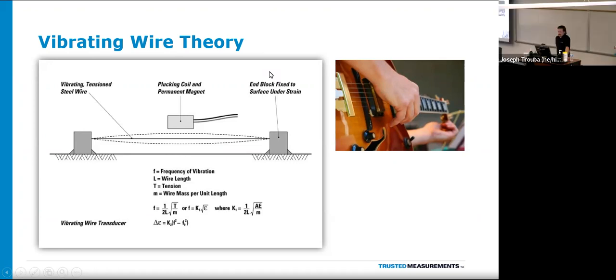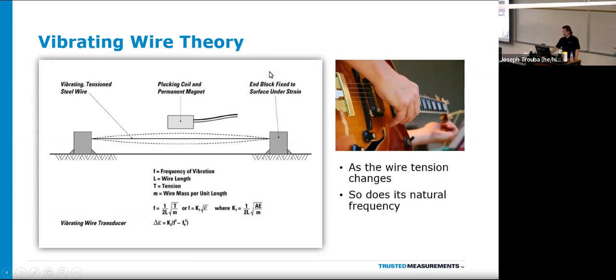And depending on the instrument, as pressure is applied to that instrument, or strain or any of the various parameters, it's going to change the frequency of that wire. As that wire elongates or shortens, it's plucked, and sends the frequency back to a data logger or a handheld readout. And those can be converted into engineering units based on the calibration information we obtain from the lab when it's made. So as the wire tension changes, so does its natural frequency.